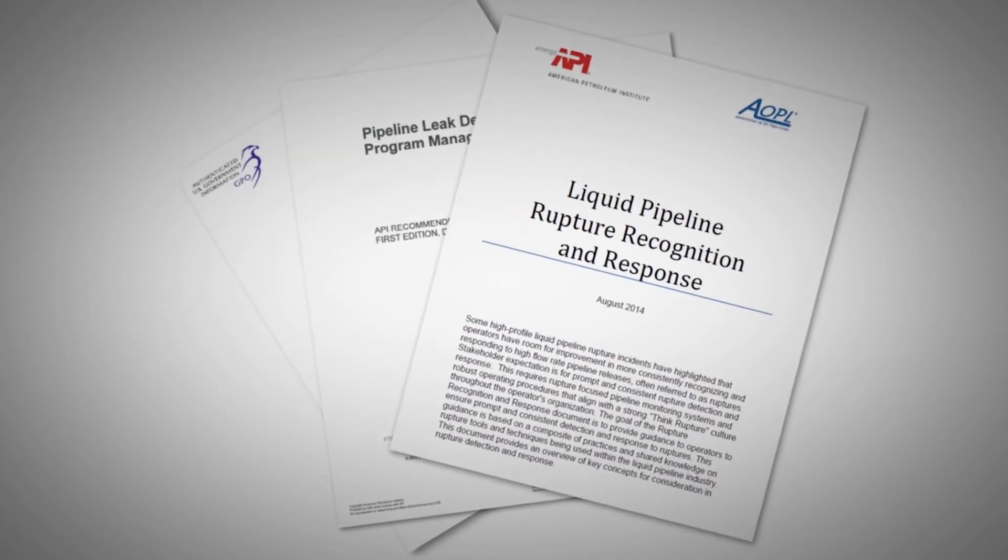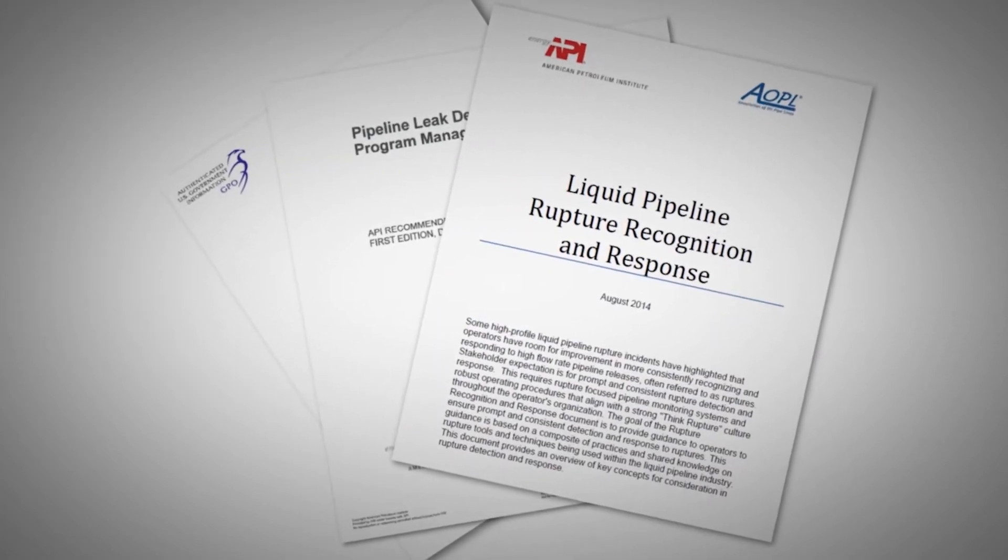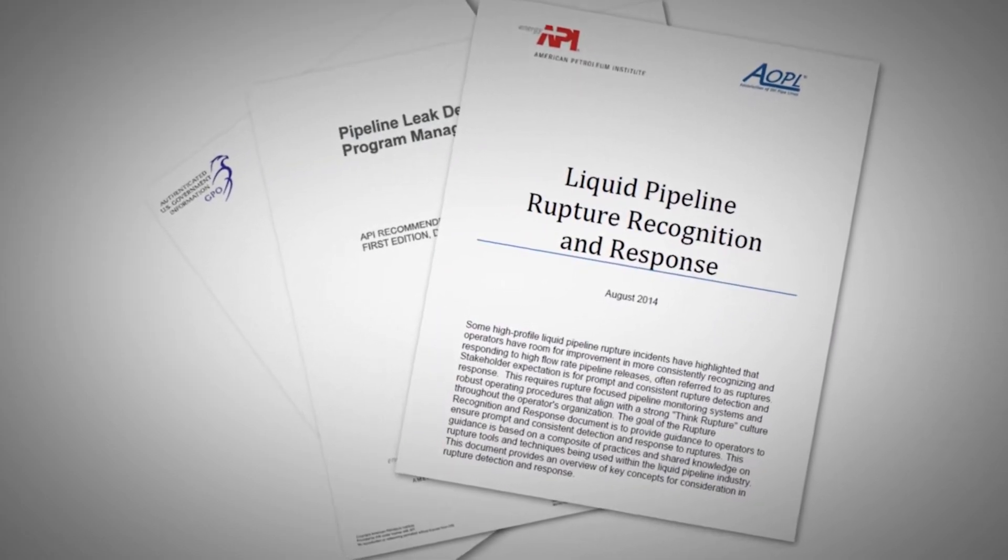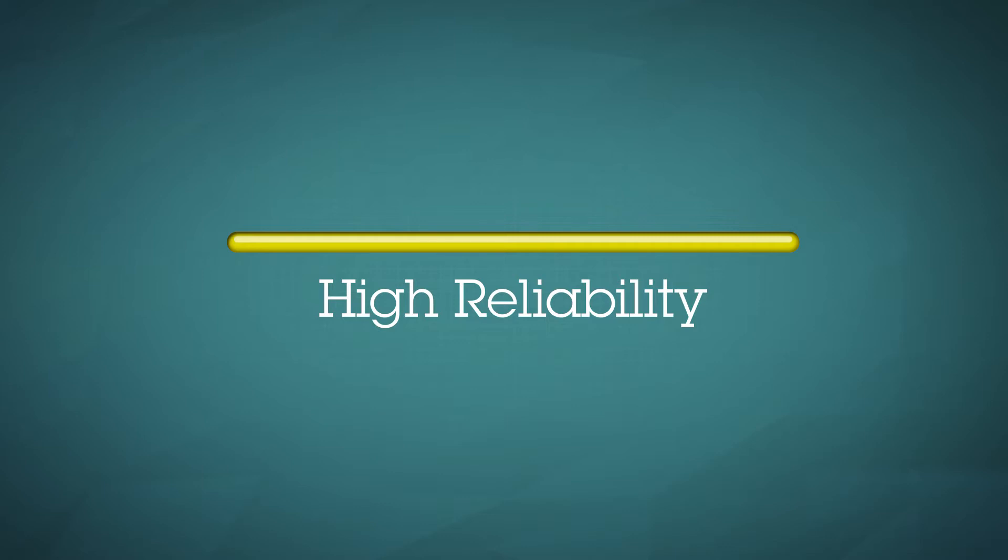Recent standards, such as the API white paper on rupture recognition and response, recommend that rupture alarms should not be treated like leak alarms. Any rupture detection system must be extremely reliable if operators are to have confidence in rupture alarms to initiate accelerated or automated shutdowns. No false alarms are acceptable.